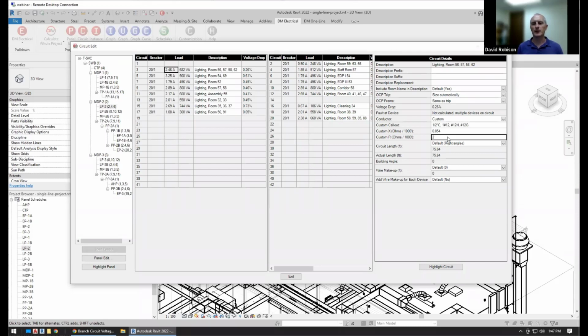Two common examples would be a bus gutter, probably not for branch circuits, that's more for feeders, or where you have multiple parallel runs and you're putting them in a single conduit rather than separate conduits. We don't actually have a way to specify that in the software, so you have to do that with a custom callout. And then the wires end up being derated a little bit because you have a bunch of wires in that one conduit. Once you enter the custom callout, you set the impedance values, the X and the R, for whatever that configuration is. And then we'll use that for our calculations.